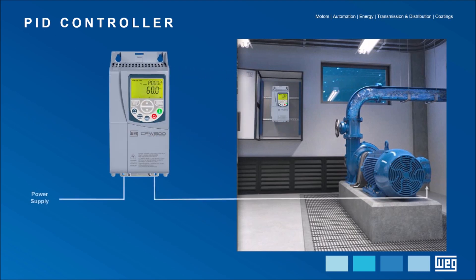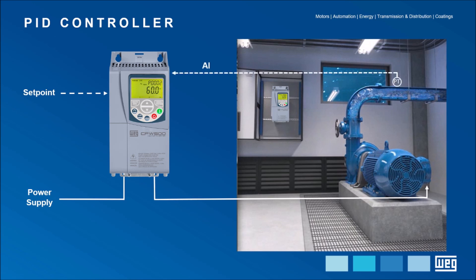We will present how to control the outlet pressure at the pipeline of a pumping system. We will have a reference point that is the desired value, also called a set point. We will also have a measured value, that is the process variable. In this application, the inverter will control the motor speed in order to keep the measured value equal to the desired value.